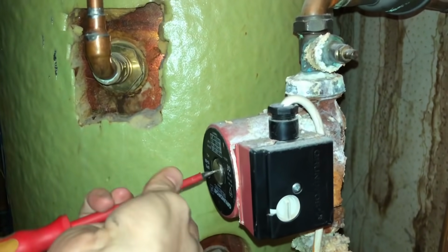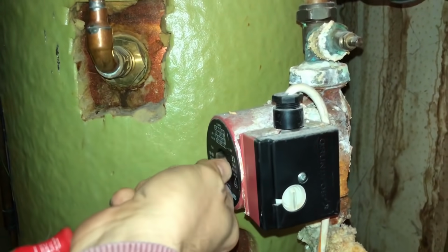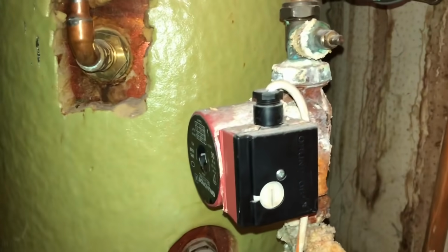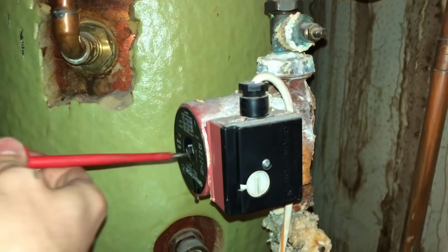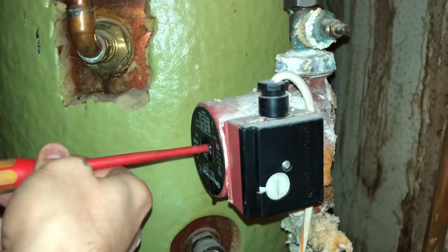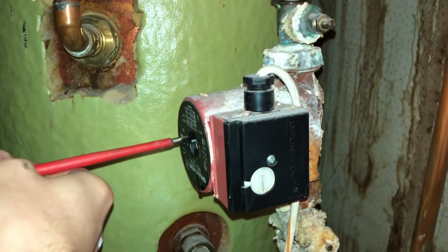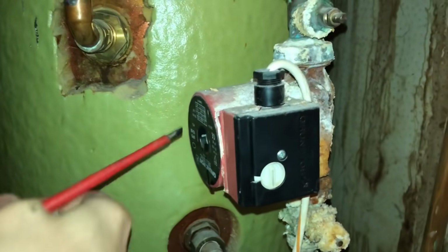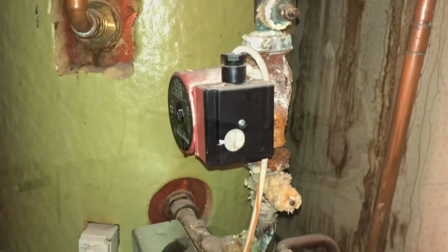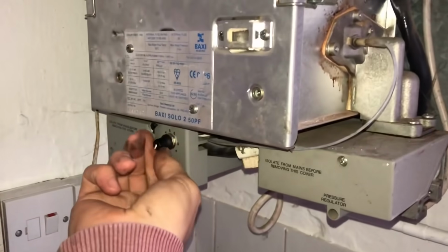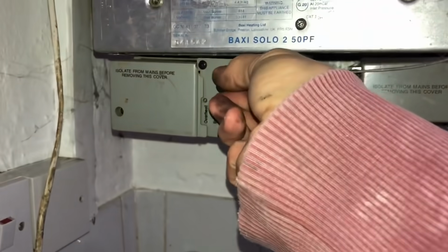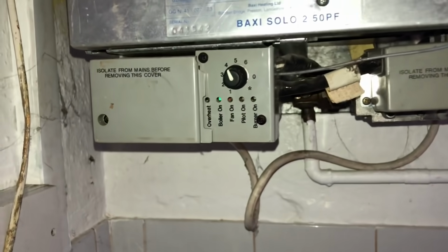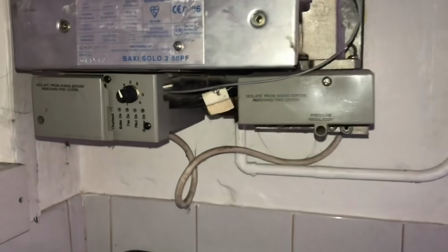Now you will need to put a rag down or a bowl, because there will be water coming out, especially if this was on. When you get it, it will be absolutely scalding hot and you'll get water or even steam, really hot water out. So you can see there, you shouldn't be able to stop a healthy pump that easily by putting a screwdriver into it. That's a great way of testing. So this job's going to have a new pump, and then I'm just going to show you here, resetting the boiler, turn it to 0 and back up again clears the fault. But I'll be fitting a new pump on this next week.